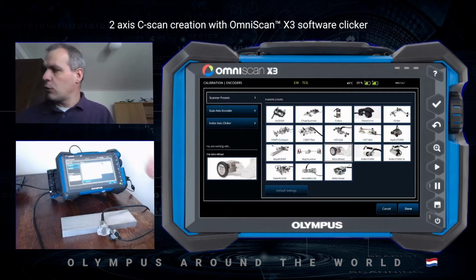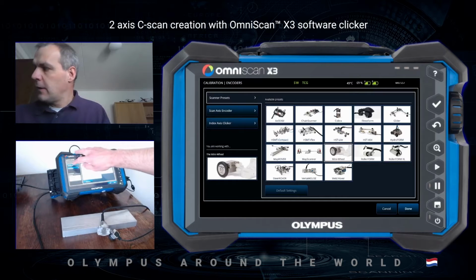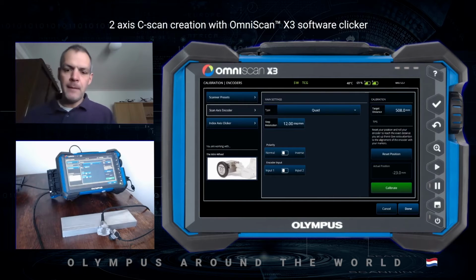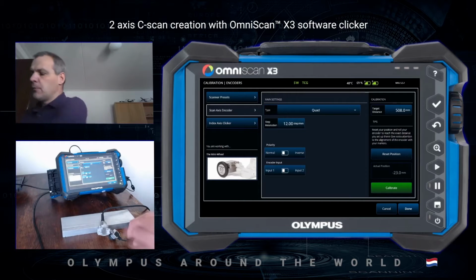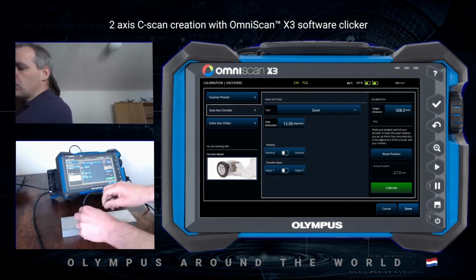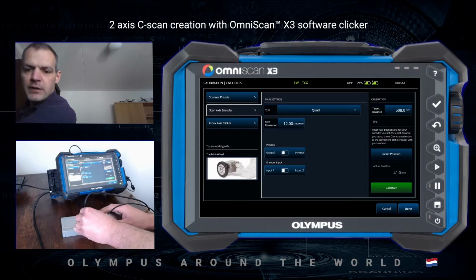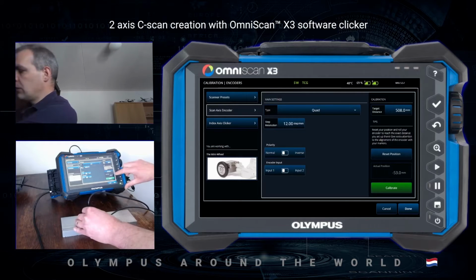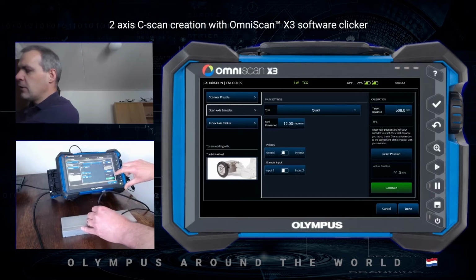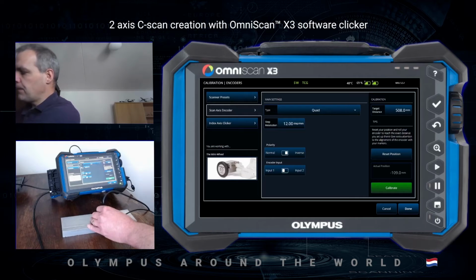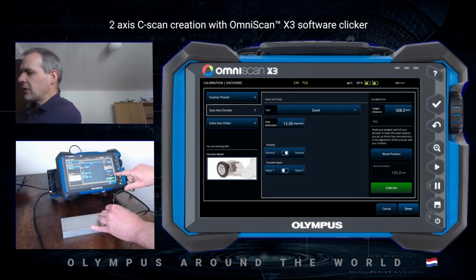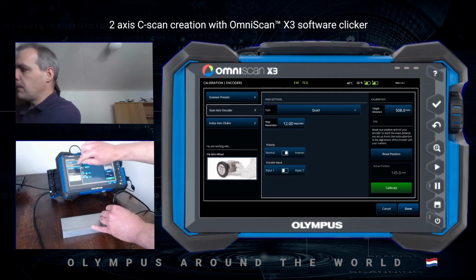select the mini wheel encoder and verify in the Scan Axis Encoder tab if the encoder moves in the right direction. Simply place the probe and the encoder on your object and move it in the scan direction and look to the actual position. In this case it counts down, so it moves in the wrong direction. I have to change the polarity. Now I can see that it increases and it moves in the right direction, so this is now set correctly.